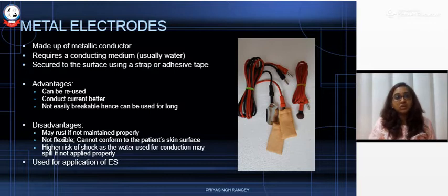You need to make sure that the electrode is very dry and that it is not kept in a humid environment. The metal electrodes are also not very flexible and hence you cannot use these kind of electrodes over all the body surfaces since they are not going to conform according to the body contour. There is a higher risk of shock because firstly the metal we are using is a really good conductor and secondly we are using water. There might be spillage of water due to accident.